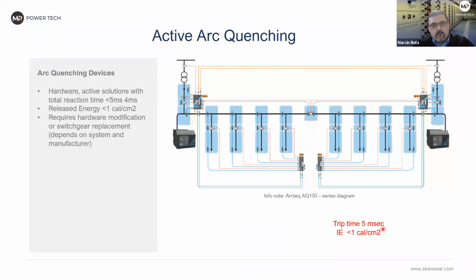The same system can be equipped also with arc quenching, which is a very nice solution. It doesn't matter who is doing this. It has to be very fast, less than a quarter cycle, so less than 5 milliseconds, to keep the system below 1 calorie. And what is worth mentioning here is that this is the only system that, when we talk about arc flash, protects people and equipment as well.